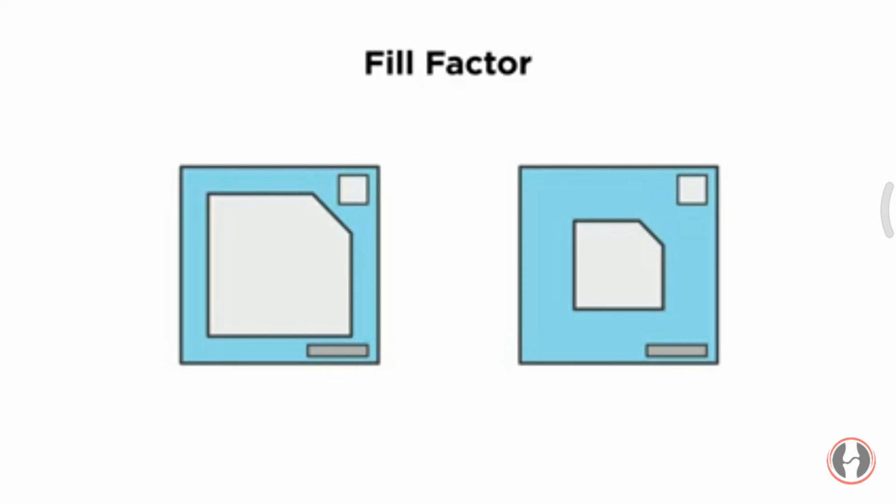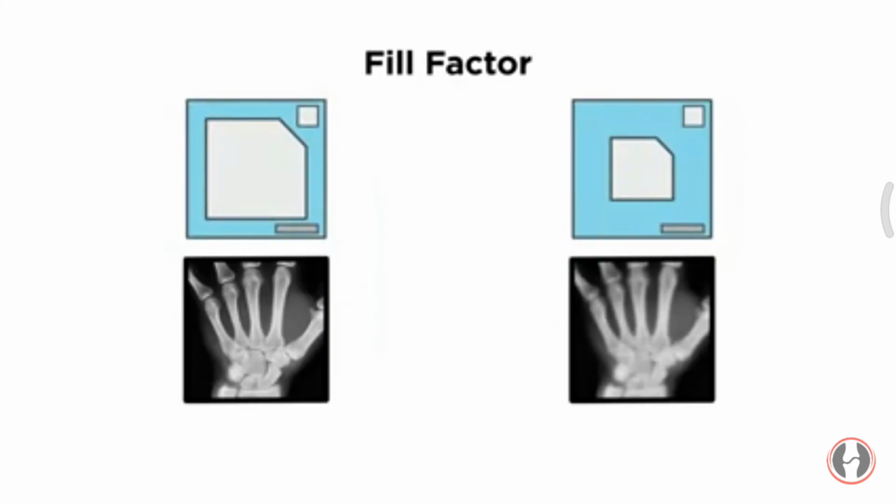The percentage of DEL to active pixel is known as the fill factor. There is a direct relationship between fill factor and spatial resolution in that as the active area increases, that is, takes up a greater percentage of space within the DEL, spatial resolution increases.